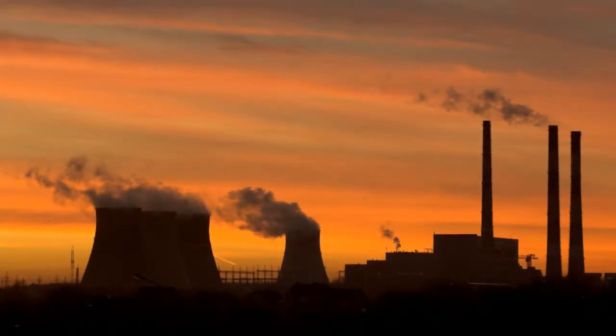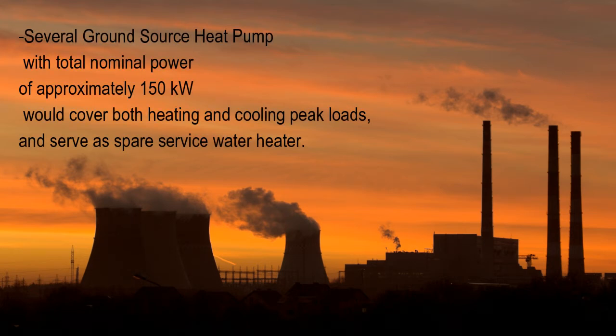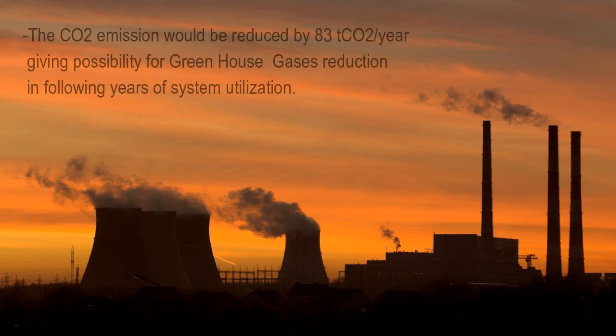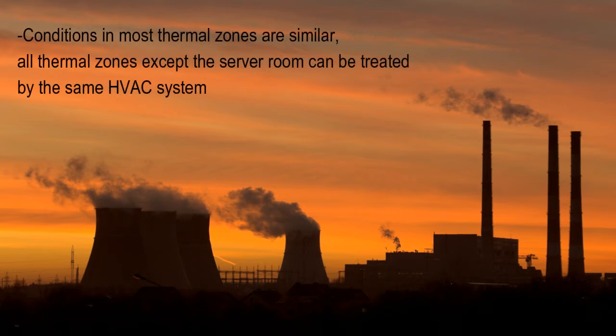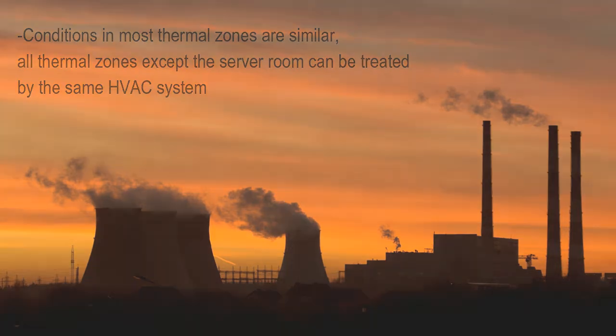In addition, there are more arguments in favor of selecting the ground source heat pump system, which are several ground source heat pumps with total nominal power 150 kilowatts could cover both heating and cooling peak loads and serve as a spare service water heater. If combined with PV panels of 32 kilowatts, the CO2 emission would be reduced by 45 tons of CO2 per year, giving the possibility for greenhouse gases reduction in the following years of system utilization. Conditions in most thermal zones are similar. This means that all thermal zones except the server room can be treated by the same HVAC system.